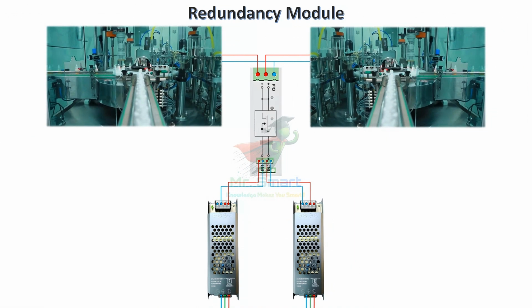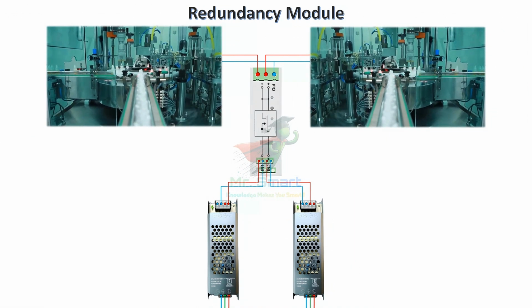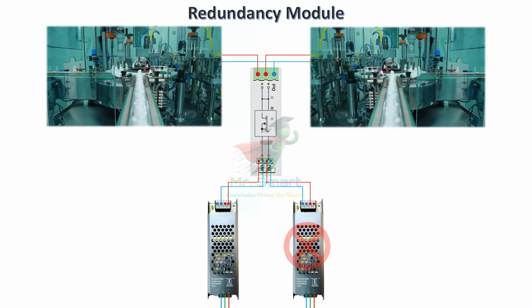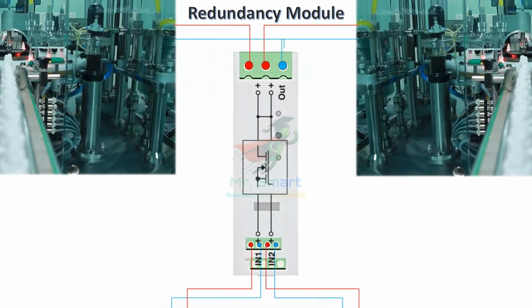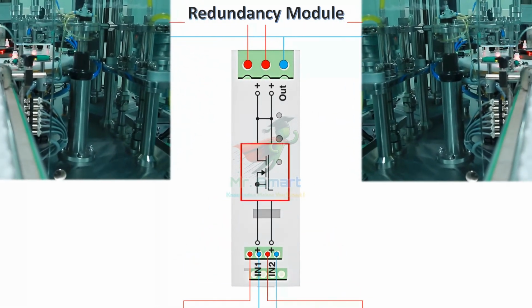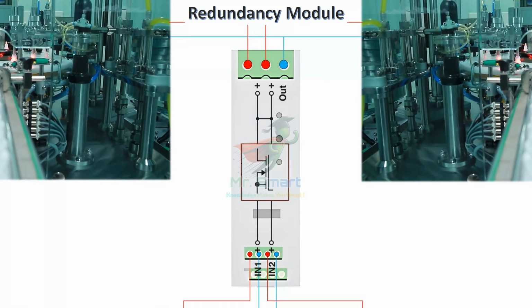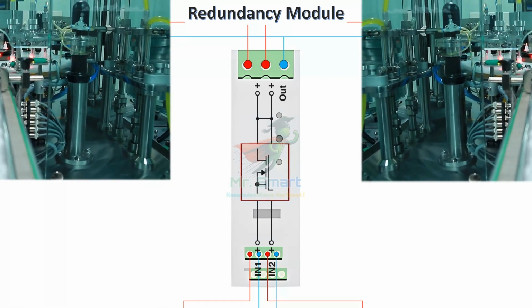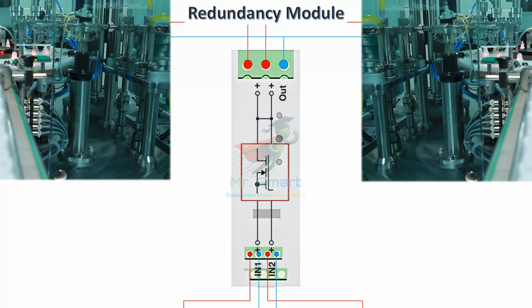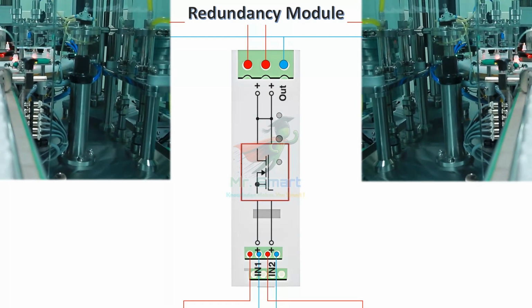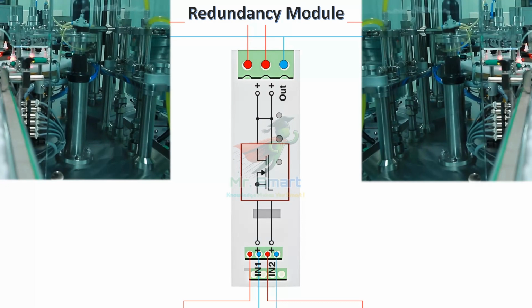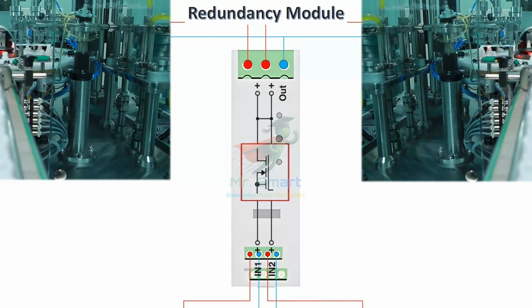We know that current naturally flows from a higher potential to a lower potential. If one power module is faulty or has a lower potential than another, the current will attempt to flow between the modules, potentially causing damage to them. The diodes or circuits in the control unit of the redundancy module prevent backflow of current between power modules, ensuring safety. Also, this unit manages the power transition during a failure and tracks the health of each power module.